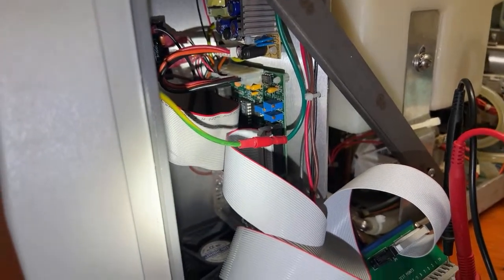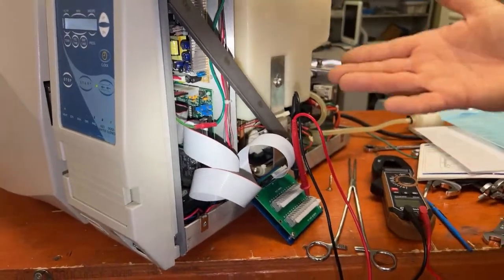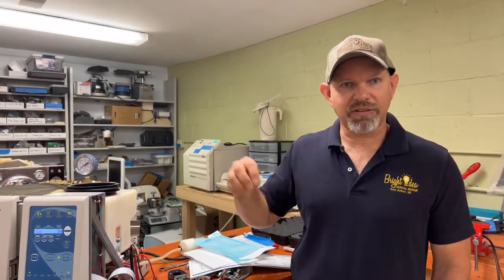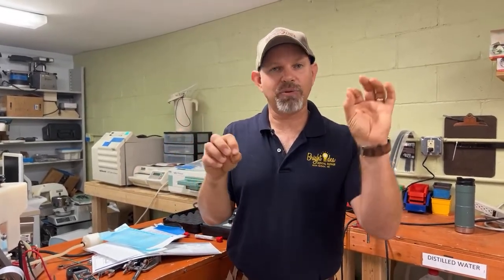What that does is take signals in from everywhere, so it has inputs and outputs. For instance, on this particular board, one of the inputs would be a pressure transducer, because that's telling the machine what the pressure is. Another input could be a temperature sensor, telling it what the temperature is inside the chamber. Another input could be the door sensor, telling the board your door's closed, your door's open. So a piece of equipment like this basically has a brain, with all the little things hooked into it, some going in, some going out. With regard to troubleshooting equipment like this, if you can isolate what sort of problem you're having, that's going to help you understand what likely culprit could be causing it.